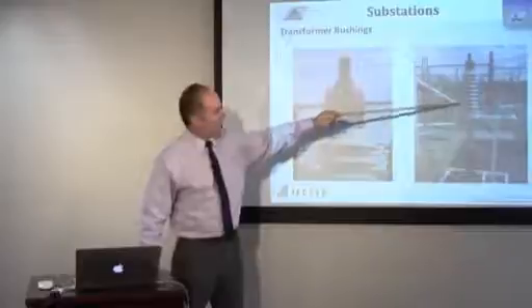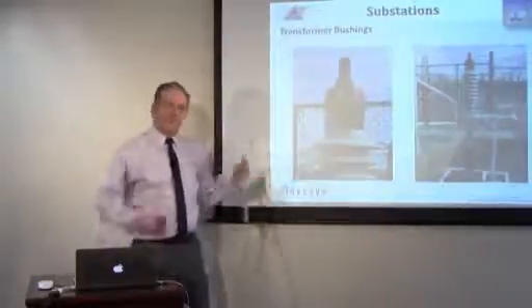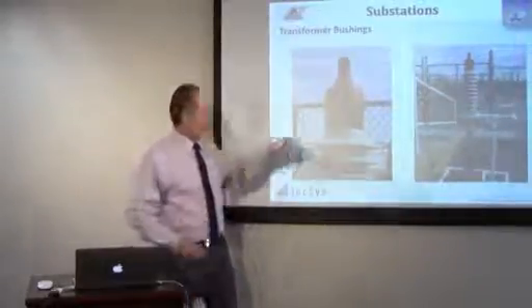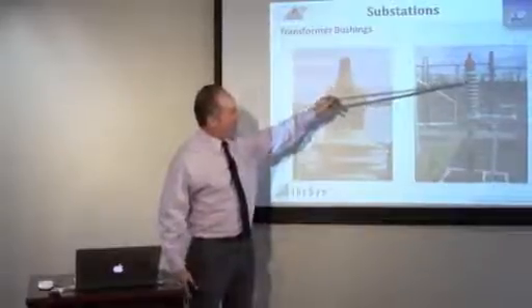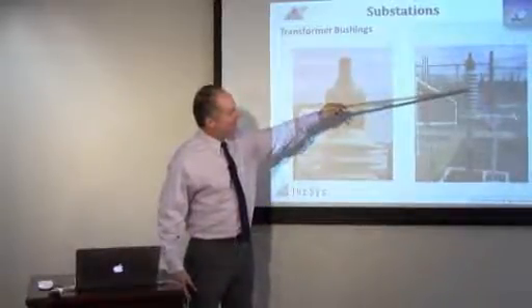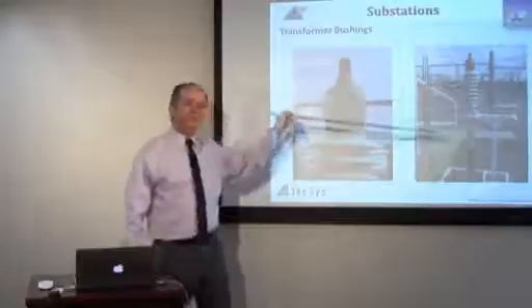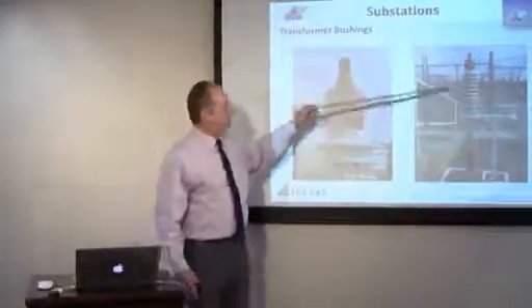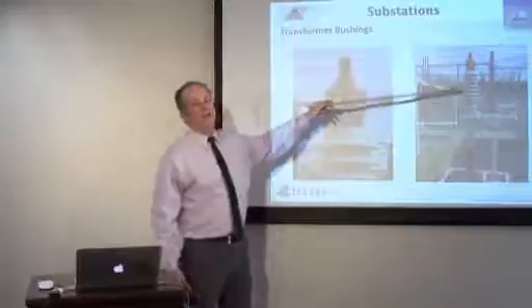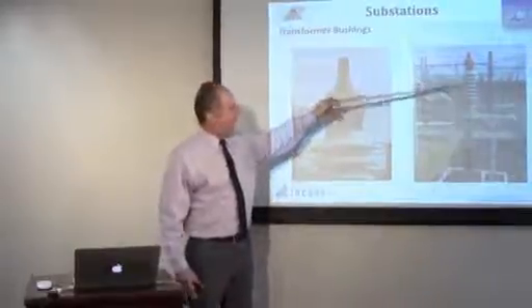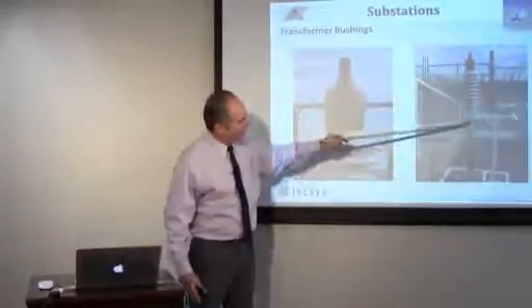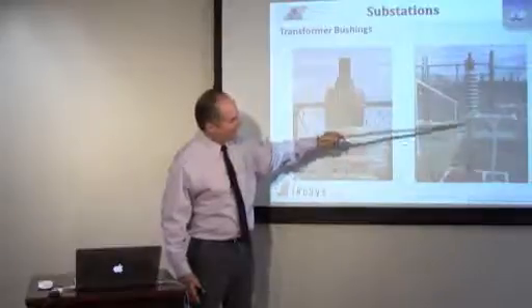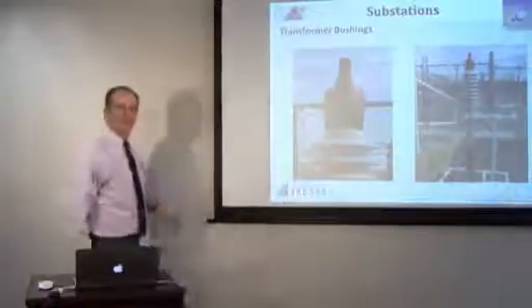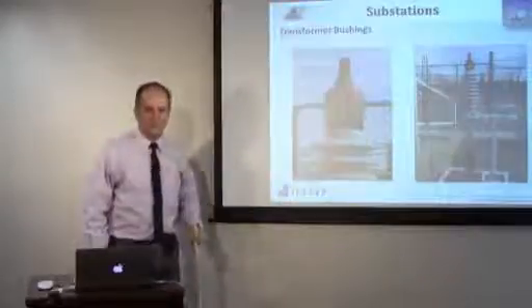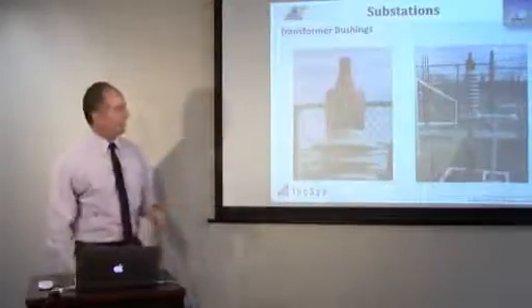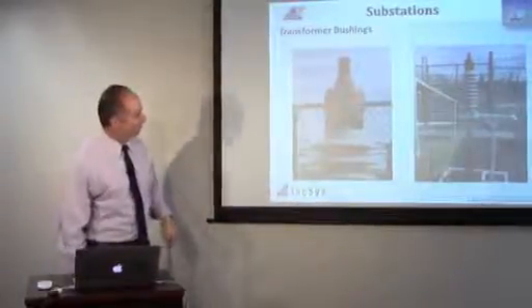If it arcs, you're making the leakage currents greater because you've reduced its path distance. So the skirts here are to reduce the leakage current in order to avoid scintillation activity and even a line to ground fault. Whereas inside the transformer or circuit breaker, you don't have exposure to the outside, so you don't need all the skirts and the ribs to make leakage paths longer. Okay, those are bushings.